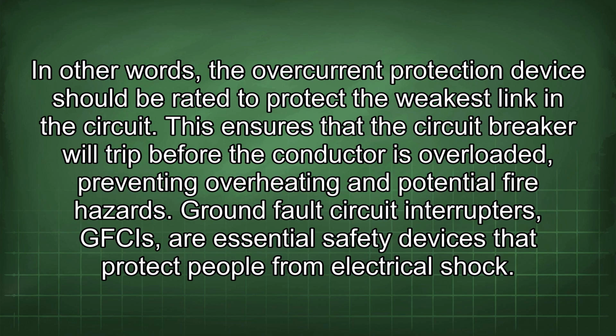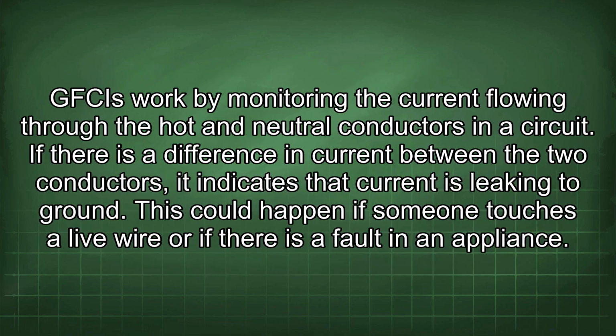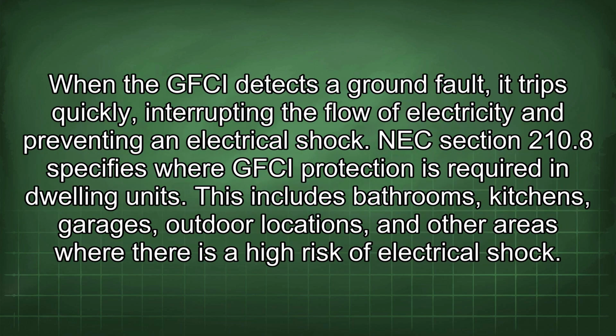Ground fault circuit interrupters, GFCIs, are essential safety devices that protect people from electrical shock. GFCIs work by monitoring the current flowing through the hot and neutral conductors in a circuit. If there is a difference in current between the two conductors, it indicates that current is leaking to ground. This could happen if someone touches a live wire or if there is a fault in an appliance. When the GFCI detects a ground fault, it trips quickly, interrupting the flow of electricity and preventing an electrical shock.